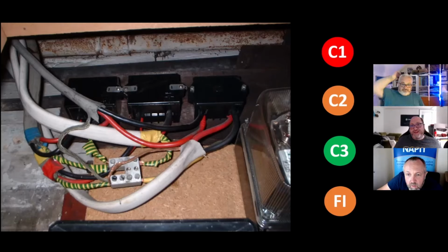No, it's not, a C2 minimum for me. C2 because you've got single insulated cable on the side of the enclosure, so that gives you a C2 straight away. The cables aren't supported, so someone could wiggle them around and they'll soon pop out of those blocks, or issues. The earth marshalling block, if you could jokably call it that, seems to be hanging in the breeze as well, so that would need to be adequately fixed for me.